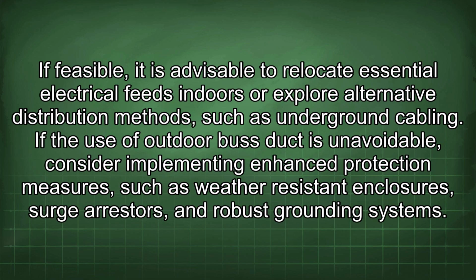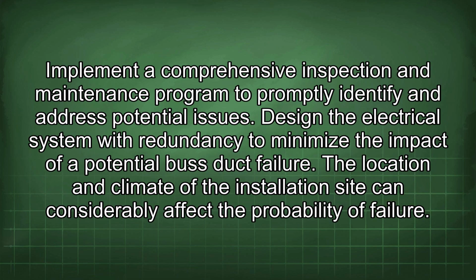If feasible, it is advisable to relocate essential electrical feeds indoors or explore alternative distribution methods such as underground cabling. If the use of outdoor bus duct is unavoidable, consider implementing enhanced protection measures such as weather-resistant enclosures, surge arresters, and robust grounding systems. Implement a comprehensive inspection and maintenance program to promptly identify and address potential issues. Design the electrical system with redundancy to minimize the impact of a potential bus duct failure.